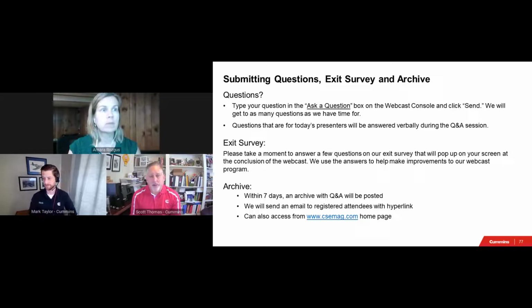Thanks, Amara. This is a very common question that we get in the field. The short answer, and I think Mark covered this very well in the presentation, is yes, natural gas generators can be used in legally required applications. If you're considering using a natural gas generator in a legally required application, there's three things I would check on. Number one, the manufacturers that you've got listed in your specification, verify that those manufacturers can meet the 10-second start requirement.